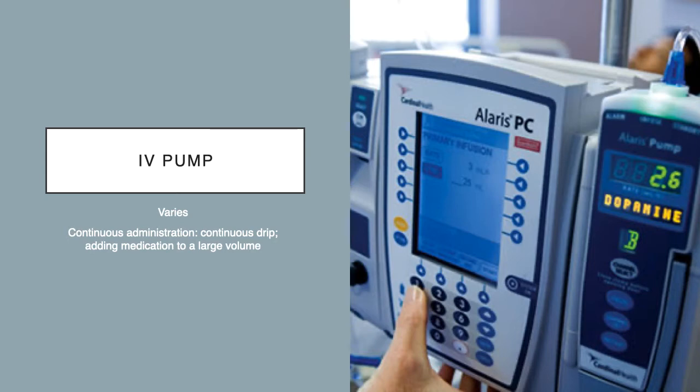But if you look at the pump and you decide that there is something going on with this pump that you cannot fix, make sure that you remove the pump from use. That's right. Take the pump out of the patient's room, get another pump for the patient, and send that pump for repair. Do not continue to use a pump that could be flawed, because you can have a medication error occur that way.